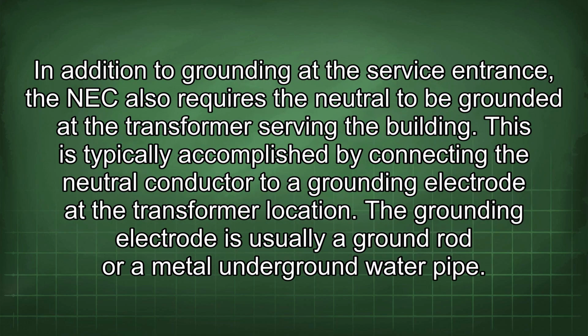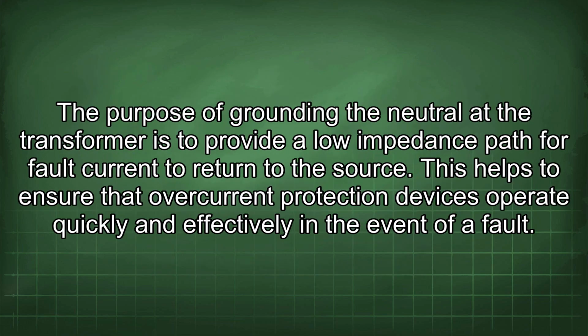In addition to grounding at the service entrance, the NEC also requires the neutral to be grounded at the transformer serving the building. This is typically accomplished by connecting the neutral conductor to a grounding electrode at the transformer location. The grounding electrode is usually a ground rod or a metal underground water pipe. The purpose of grounding the neutral at the transformer is to provide a low impedance path for fault current to return to the source. This helps to ensure that overcurrent protection devices operate quickly and effectively in the event of a fault.